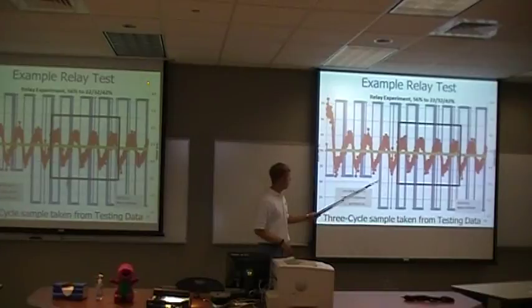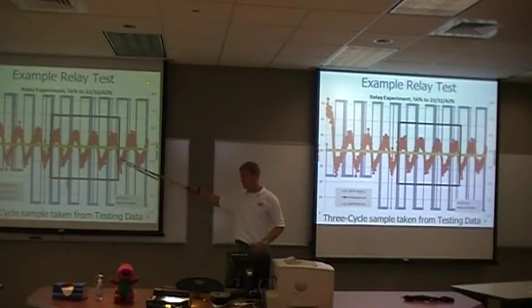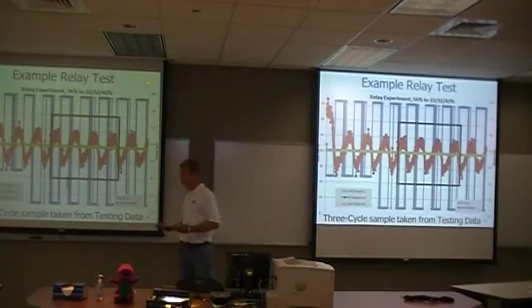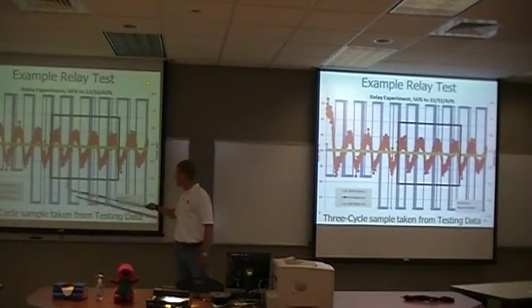Also, I want to note that I think Josh Solomon had a question about why that did not change whenever we changed the ceiling. So I was going to get back to you on that. Our system stops at 39%. It doesn't really stop. It quits producing water because of the friction in the pipes and the vertical head of our system. And so that's why it never changes, because at 20 it's just the same thing as 39.